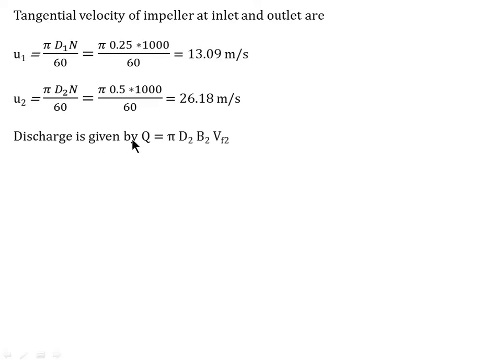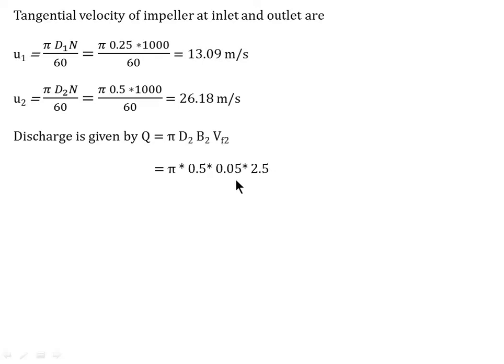Discharge Q is calculated by the formula: Q equals pi × D2 × B2 × Vf2. In centrifugal pumps, area equals pi × diameter × width, and discharge equals area × flow velocity. Substituting D2 equals 0.5 m, B2 equals 0.05 m, and Vf2 equals 2.5 m/s, we get Q equals 0.1963 meter cube per second.